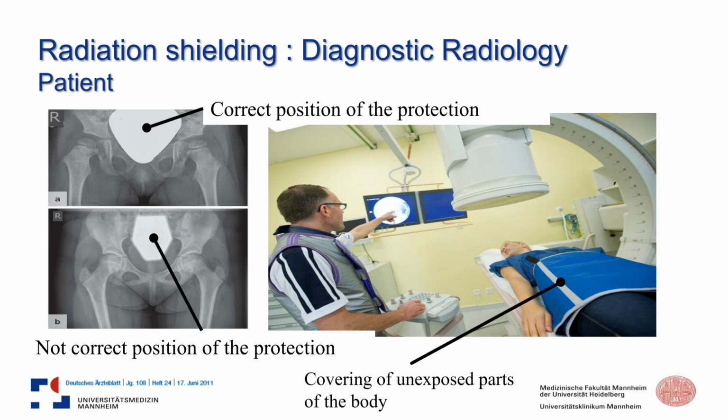So you see, if you want to shield the patients, at the left-hand side is an example for shielding the gonads. If you put a shielding protector, in this case the equivalent of 1 millimeter lead, you could shield this part of the body in the primary beam by 100%. A typical energy in radiodiagnostics to do these images is 80 kV or 90 kV.